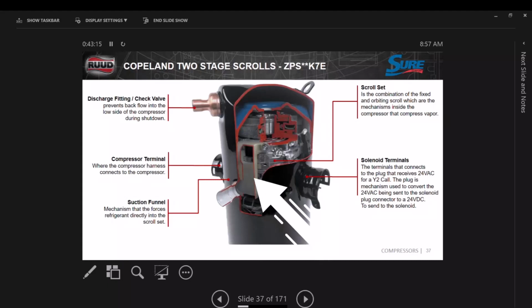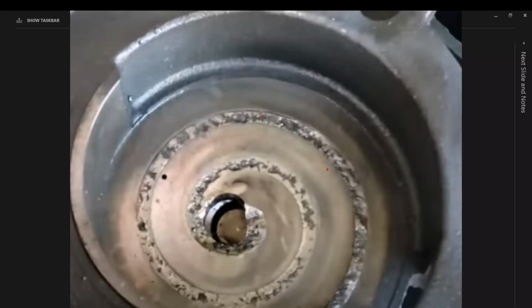And right here at the bottom, we got this little device called a suction funnel. Now, a suction funnel takes all the suction gas, and remember I said gas, right, not liquid, and forces it up to the scroll plate. Where before, the suction gas would come in and kind of drop to the bottom. If it had any liquid in it, the heat of the motor down here would dissipate it. It no longer does that. It comes in and goes straight to the scroll plate. So if we're charging this unit, let's say you open the valves up in the winter and immediately turn on this unit. You're going to get a slug of liquid through here. And when you do, this can happen.